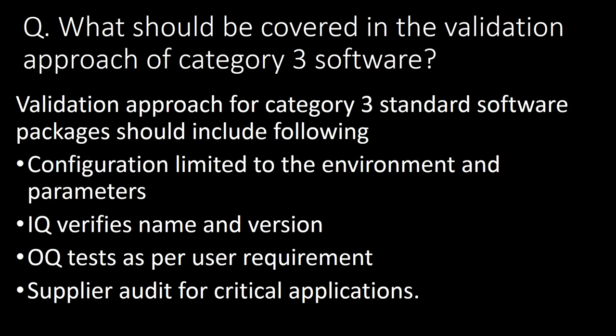What should be covered in the validation approach for category 3 softwares? The validation approach for category 3 standard software packages should include: first, configuration limited to environment and parameters; second, IQ that verifies name and version; third, OQ tested as per user requirements; and fourth, supplier audit for critical applications.